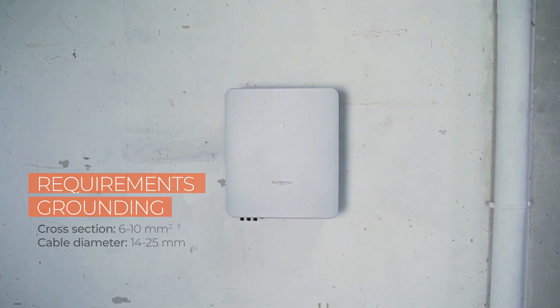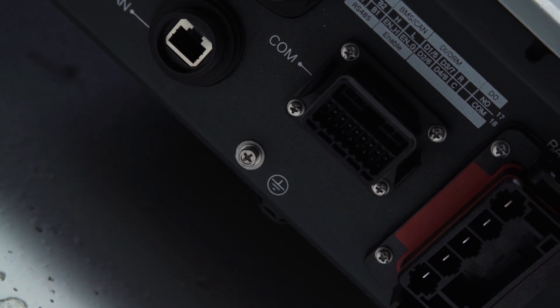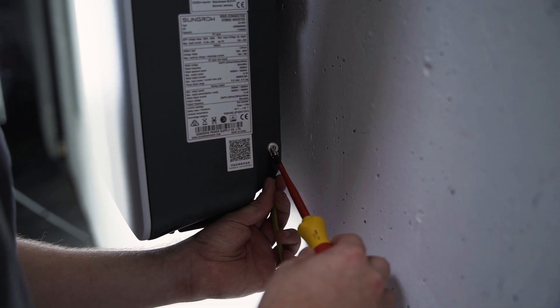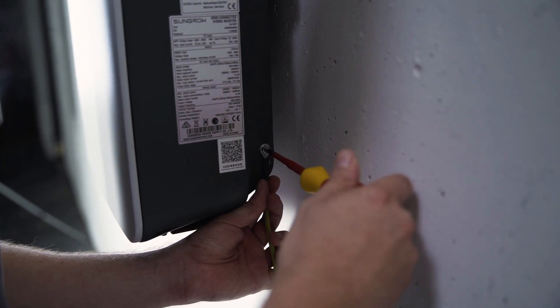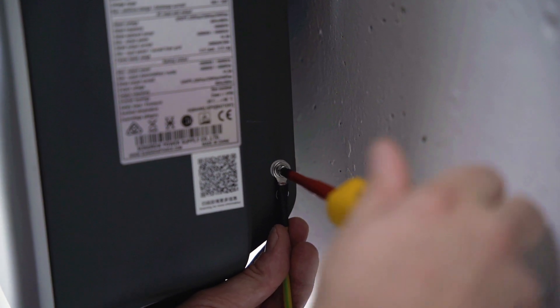In the first step you have to connect the inverter to ground. There are two PE connections, one at the bottom and one on the right side of the inverter. At least one of them has to be connected to the general grounding of the house.